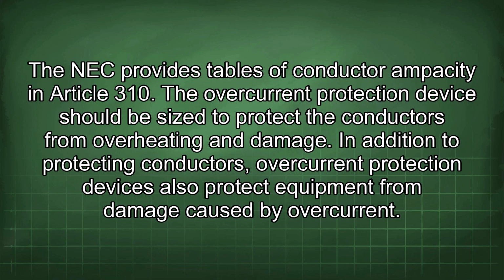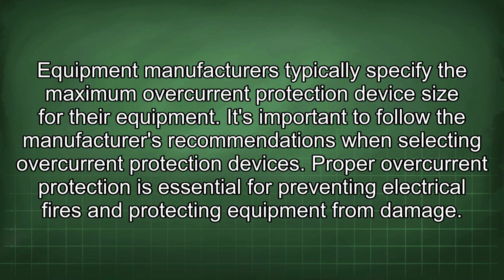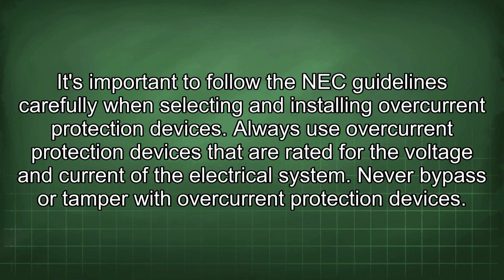In addition to protecting conductors, overcurrent protection devices also protect equipment from damage caused by overcurrent. Equipment manufacturers typically specify the maximum overcurrent protection device size for their equipment. It's important to follow the manufacturer's recommendations when selecting overcurrent protection devices. Proper overcurrent protection is essential for preventing electrical fires and protecting equipment from damage. It's important to follow the NEC guidelines carefully when selecting and installing overcurrent protection devices.